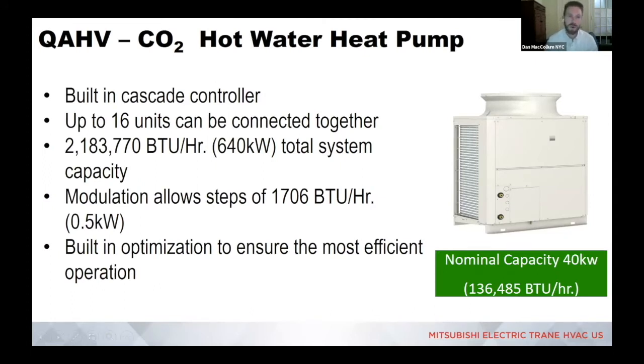The name of the game, though, with hot water heat pumps, and many people on this call are probably more familiar with this than I am, is really finding a good balance between generation and storage. So the more generation you have, or the more outdoor units you have, the less storage you'll need to satisfy your space. But the more storage you have, the less outdoor units you'll need. So it's going to be a function of your peak demands and what actually works for your building. But I do want to point out that although I don't have a storage tank shown on this, it is an integral and very important piece of the equation.